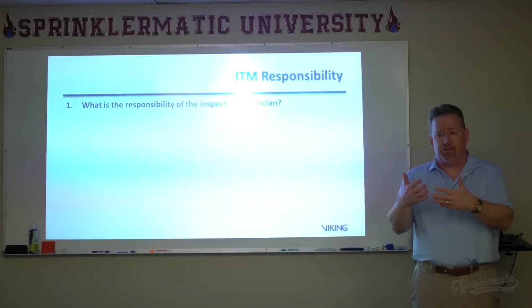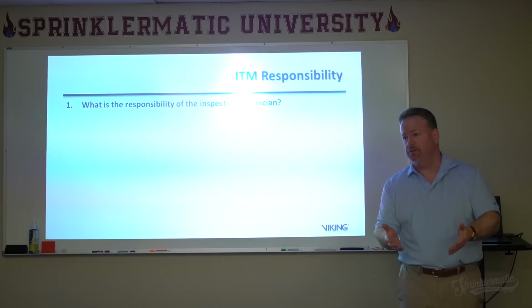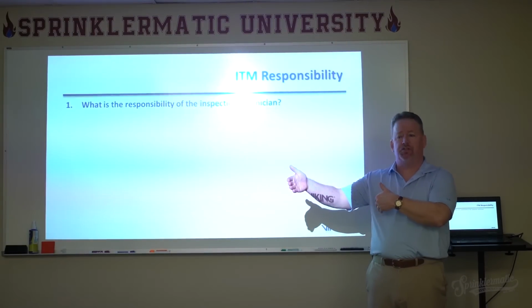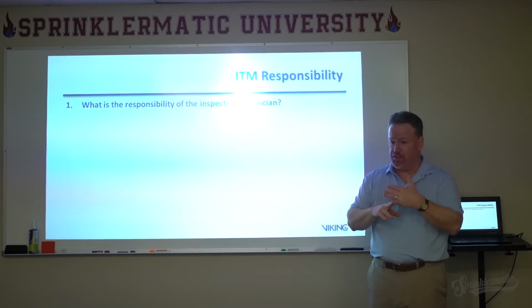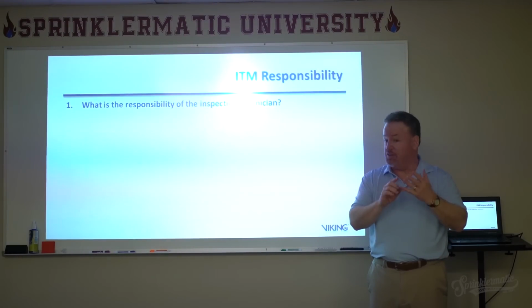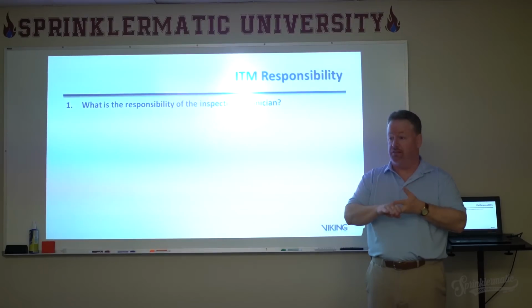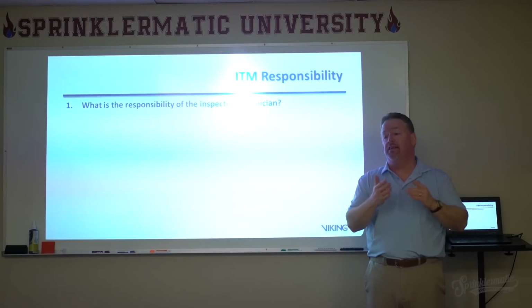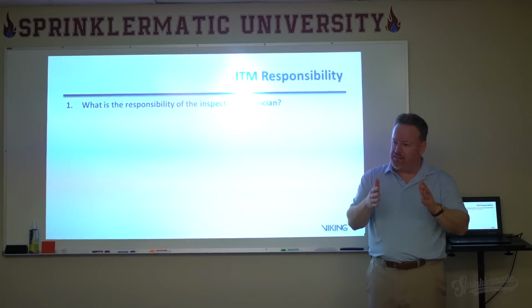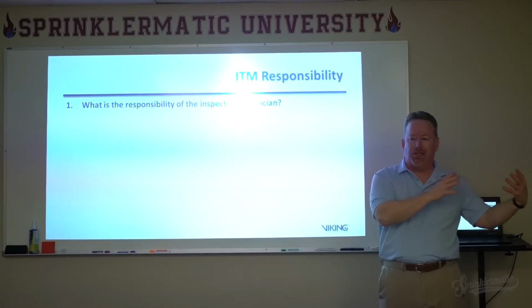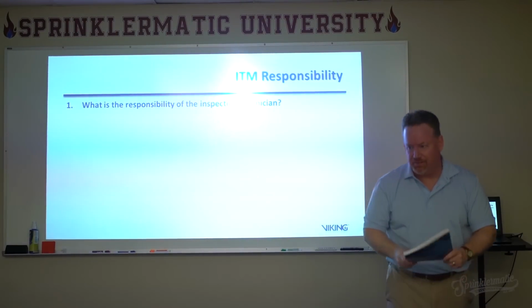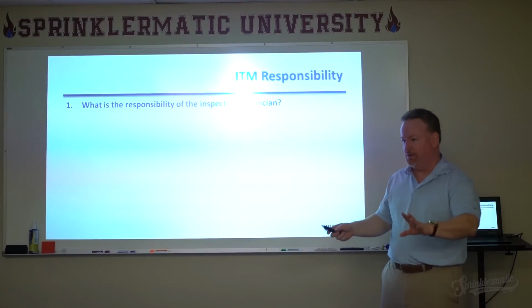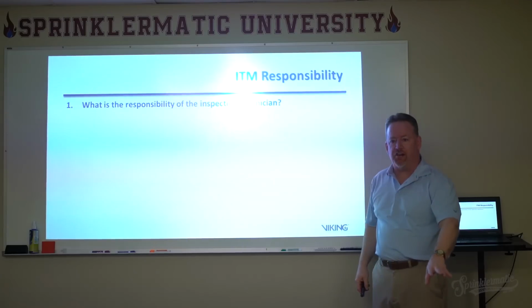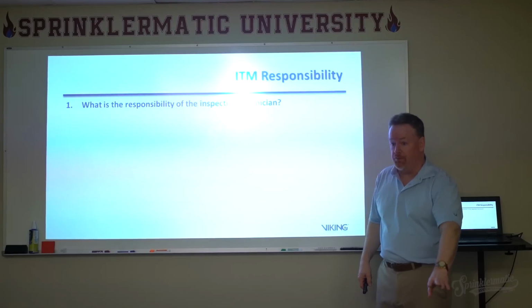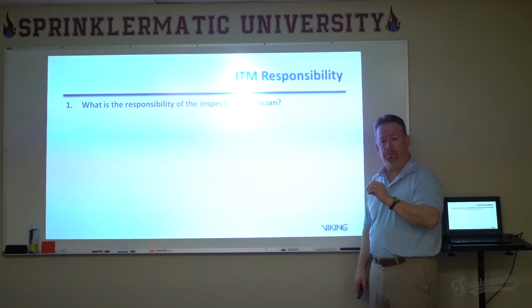So what's the responsibility of the inspection technician? Basically, it's to know NFPA 25 and apply it to the system as they're walking through it—to know what function they're there for, and what the requirements are for that function, whether it's inspection, testing, or maintenance, all of which are defined differently in NFPA 25. So the technician's responsibility is to help the owner comply with the law by applying the rules of NFPA 25—know it, apply it, fill out the forms, stay within its scope, and mostly help the owner comply with the law.